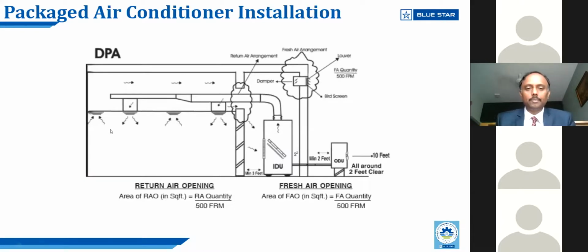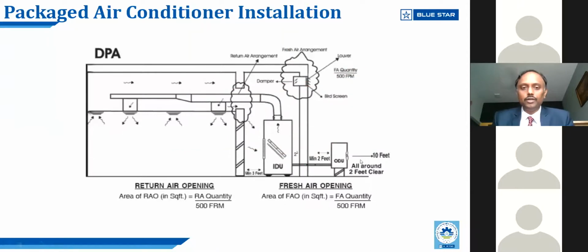Kumaresh, you can show the return air part. Now, the return air has to come back to the unit, so you need to give the return air space, which is the opening between the plant room and the conditioned space. This return air opening is very important. You need to keep it adequately designed so that the air conditioning system functions properly and efficiently. That is the most important part to keep in mind.